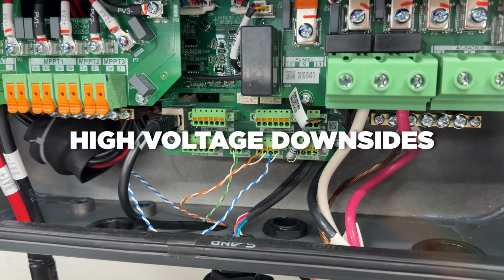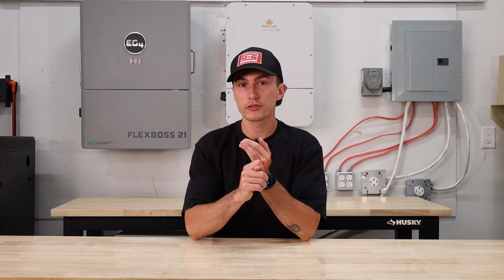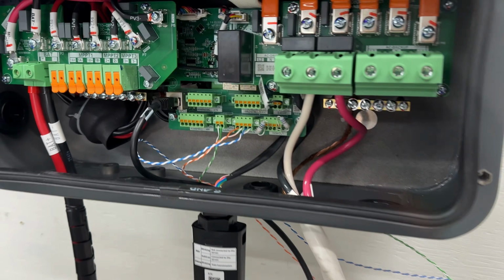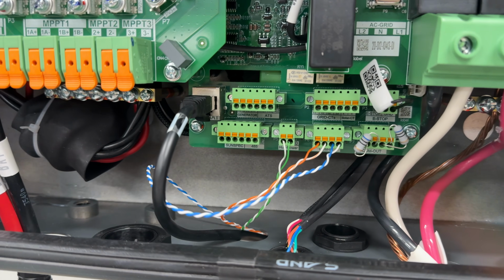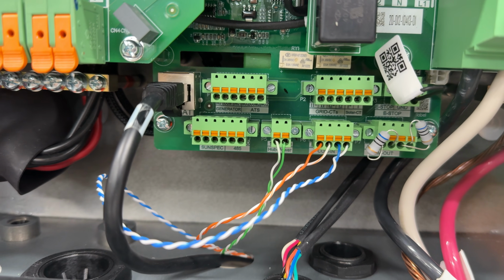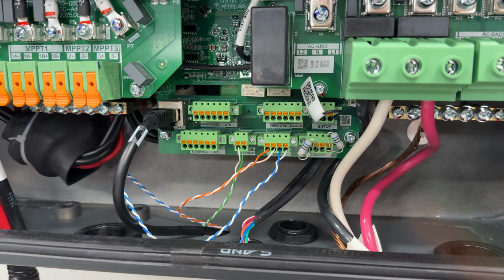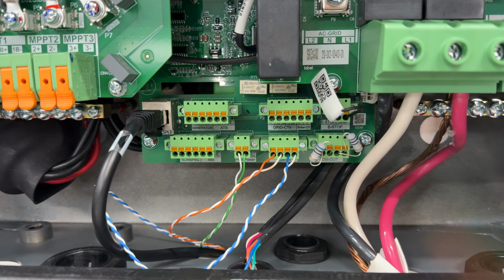When you look at the downsides of a high voltage system, we've already touched on a few. The battery chemistry and communication aren't as DIY friendly. The batteries have to communicate with the inverter for the whole system to work and for the inverter to know what's going on, because the voltage is always changing. There's a lot of custom communication stuff required too. It's not like a 48 volt system where they give you an Ethernet cable, you plug it in on both ends and it works. They actually require you to make your own, pin out your own cables sometimes for these systems, which is annoying.